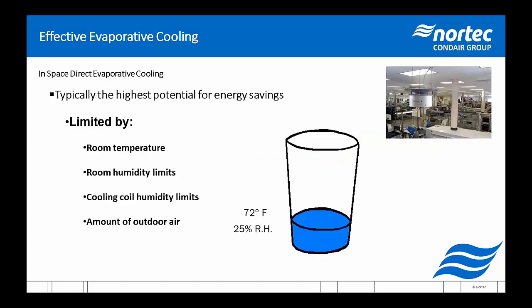Now, let's get into detail on the fun stuff. So in-space direct evaporative cooling is typically the highest potential for energy savings. Not peak load savings in most climates, but overall energy savings. Inside the room, we're limited by the room temperature. Obviously, we can't overcool, and that's typically not a problem. As well as room humidity limits. We don't want to live up to the word swamp cooling, which is not a term we typically use, mostly because we no longer consider any of this swamp cooling. We're not very swampy anymore.